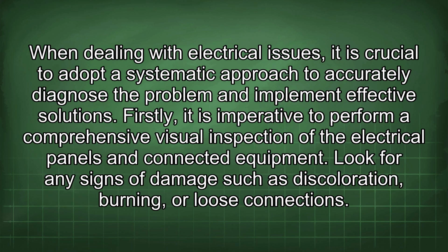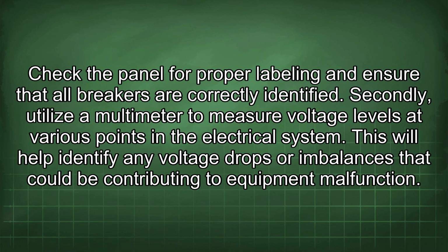When dealing with electrical issues, it is crucial to adopt a systematic approach to accurately diagnose the problem and implement effective solutions. Firstly, it is imperative to perform a comprehensive visual inspection of the electrical panels and connected equipment. Look for any signs of damage such as discoloration, burning, or loose connections. Check the panel for proper labeling and ensure that all breakers are correctly identified.